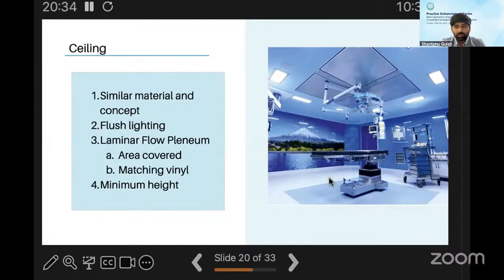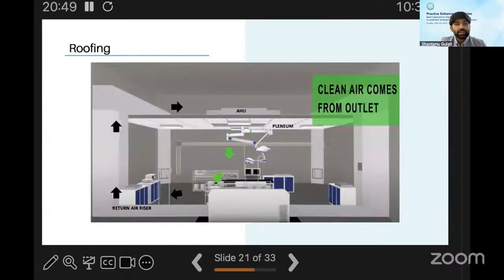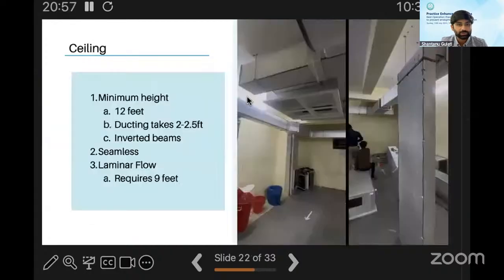your instrument sets, when they are opened from the sterile boxes, are opened below the plenum, which is why, as you can see in the image, the vinyl right below the plenum is of a different color, so that your staff knows whether they are under the laminar flow or not. This is an image showing the flow from the AHU onto the table. Then the air goes back from the return riser again into the AHU.